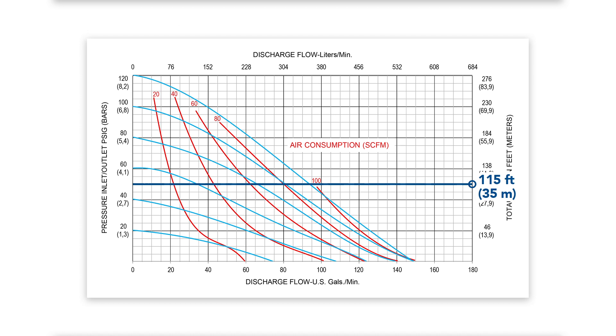Refer to the AODD pump performance curve once again and adjust the operating point to the viscosity correction flow rate of 30 gallons per minute. This allows you to reassess the new required air inlet pressure, which will be 60 PSI, as well as the increase in air consumption, which will be 30 SCFM.